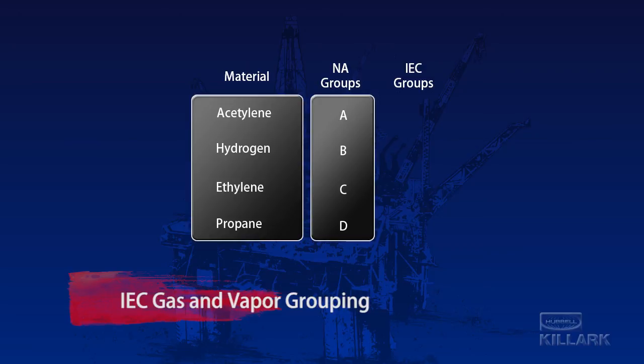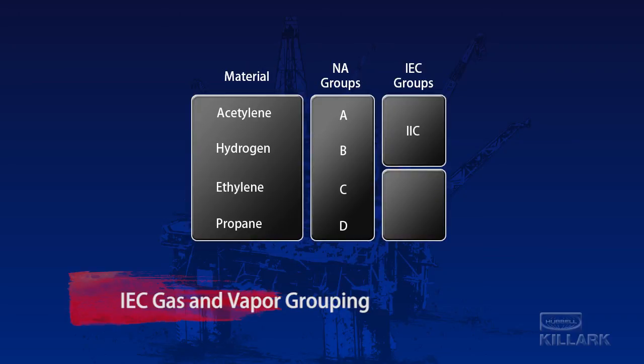And in this case, both acetylene and hydrogen-type materials are pulled together under the designation IIC. Materials similar to ethylene are Group IIB, and those that have explosive characteristics corresponding to propane are designated IIA. The Roman numeral II, appearing before each letter, indicates that these groupings of gases and vapors are not the result of underground mining. The special requirements for mining use the Roman numeral I.